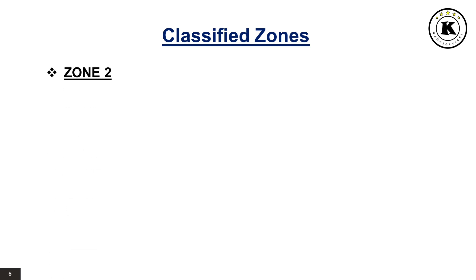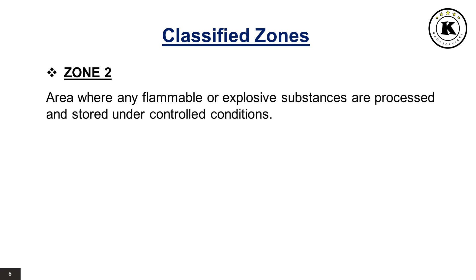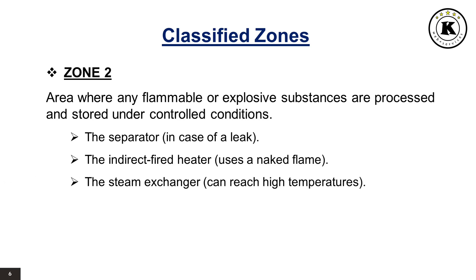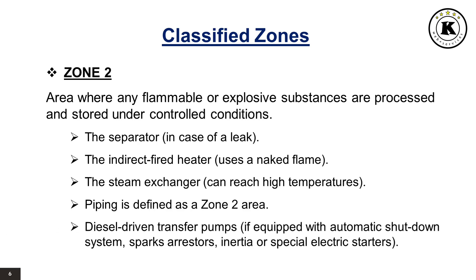Zone 2 is the area where any flammable or explosive substances are processed and stored under controlled conditions. For example, the separator in case of a leak; the indirect fired heater because it uses a naked flame; the steam exchanger because it can reach high temperatures; and piping, which is defined as a Zone 2 area. Diesel-driven transfer pumps are also Zone 2, if equipped with automatic shutdown systems, spark arresters, inertia, or special electric starters.